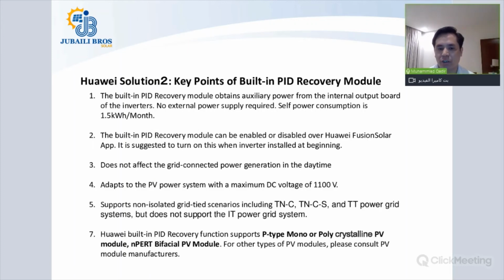So when you install and commission an inverter, you have the option of turning on and off the built-in PID recovery feature. So in areas where you are sure that there is minimal chance or no chance of PID occurring, you might be thinking of not using this feature because it consumes a little power at the end of the day. So it is suggested to turn it on when the inverter is installed at the beginning, because you can use this feature and make sure that there is no PID accumulation that will affect the production of your PV plant. So as I said earlier, I'm repeating it, it will not affect the grid connected power generation in the daytime.